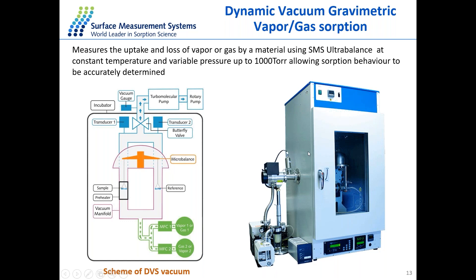One of the key benefits of this gravimetric vapor adsorption is that everything is under thermodynamic equilibrium, achieved by a temperature enclosure or incubator operating in the range of 20 to 70°C. We can generate full P/P₀ isotherms for organic solvents and water vapor. Notably, this system does not require a carrier gas — we use vacuum as the driving force for molecules to travel across the sample. We can connect a water reservoir to MFC1, and MFC2 is connected to gas such as CO2.